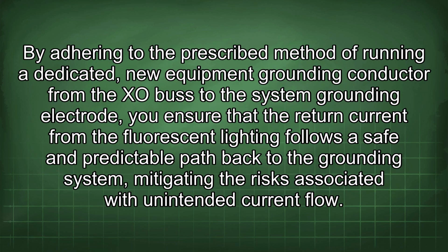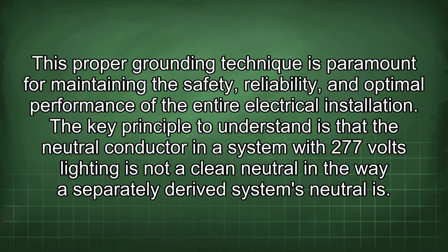By adhering to the prescribed method of running a dedicated, new equipment grounding conductor from the XO bus to the system grounding electrode, you ensure that the return current from the fluorescent lighting follows a safe and predictable path back to the grounding system, mitigating the risks associated with unintended current flow. This proper grounding technique is paramount for maintaining the safety, reliability, and optimal performance of the entire electrical installation.